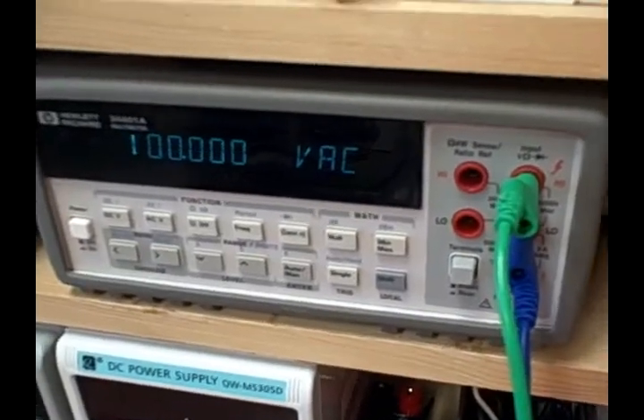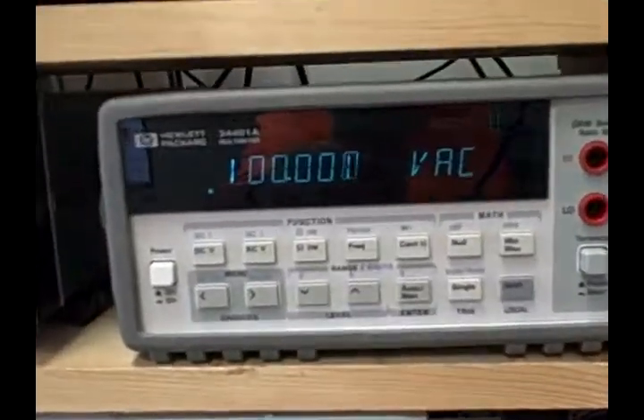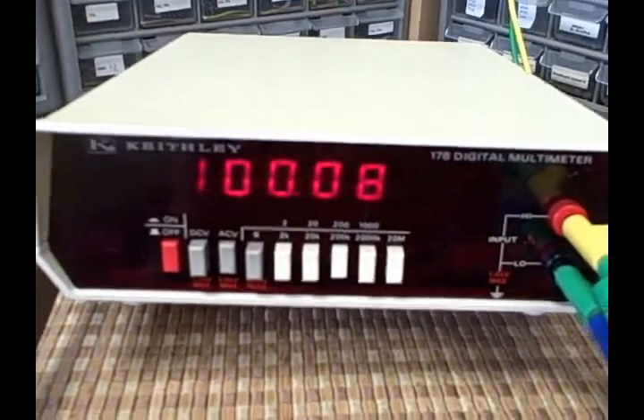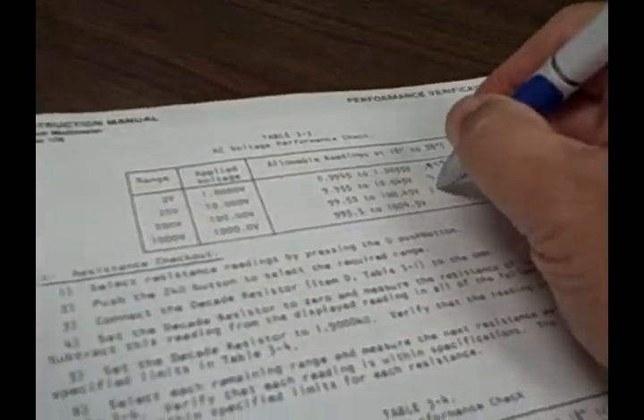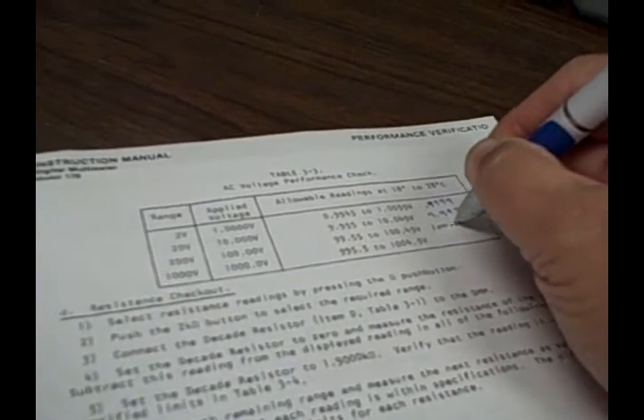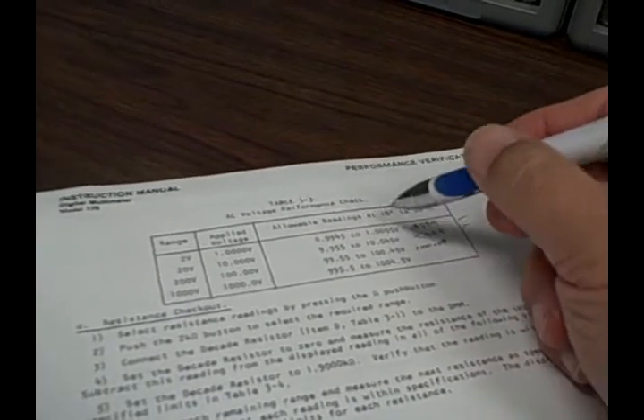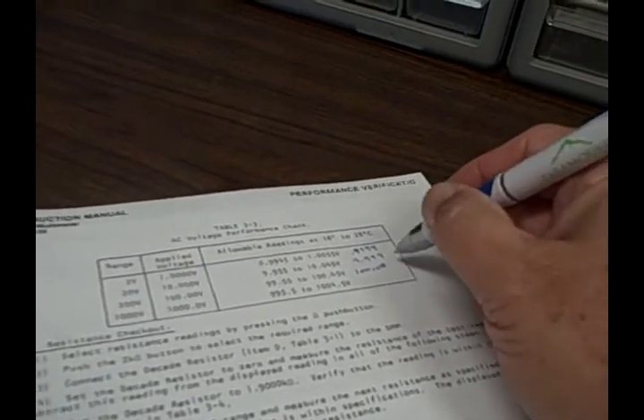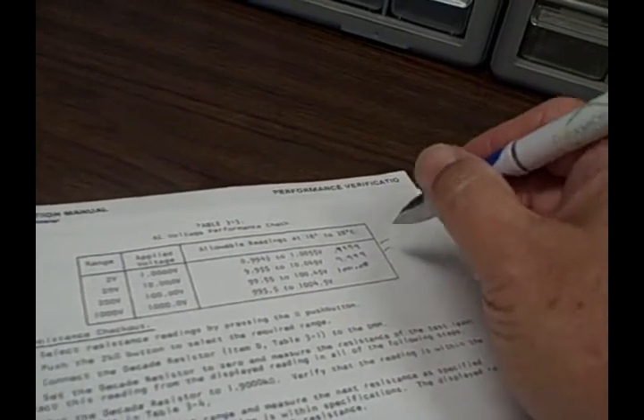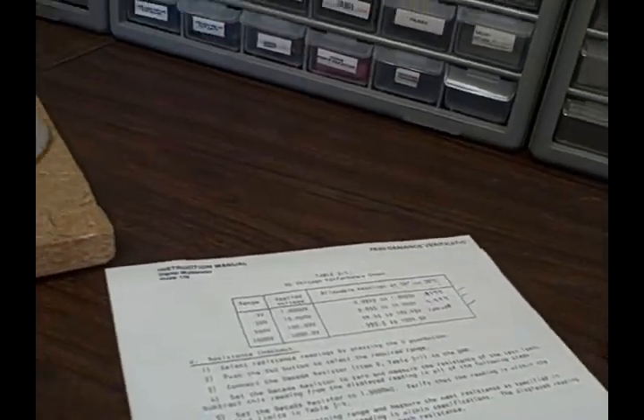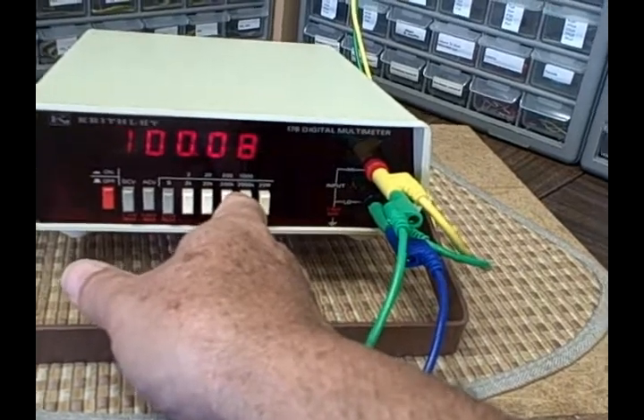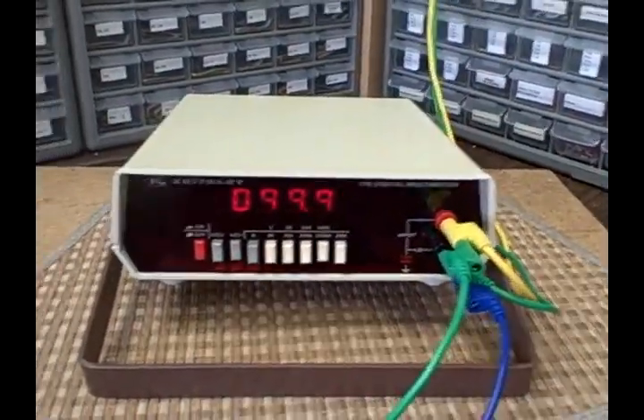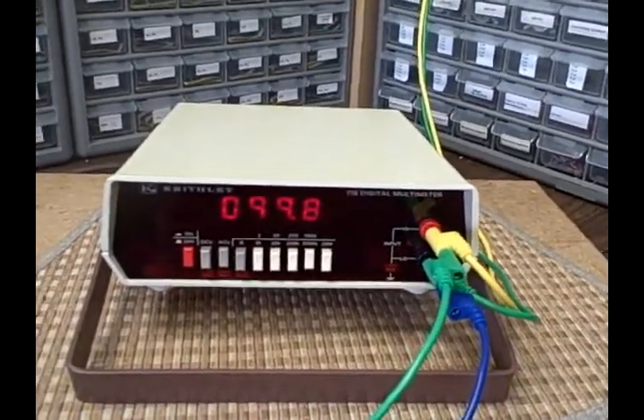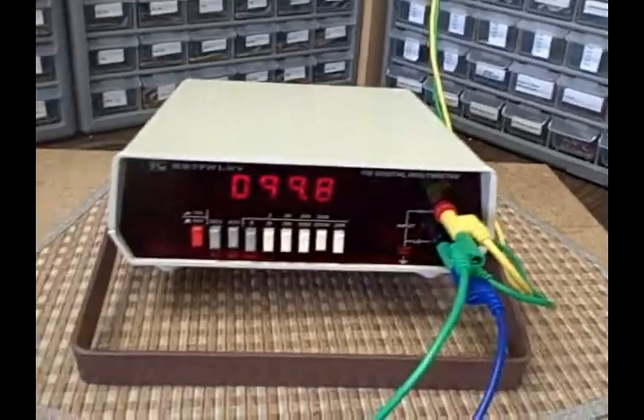Okay. All right, we got 100.000 volts AC. And we're getting a reading of 100.08. We would be accurate if we were between 99.55 to 100.45, and we're 100.08. So again, right in the middle. We are 0.08 of a volt off of perfection, but beautiful. And if we go to the 1,000 volt range, the best I'm going to be able to do here is about 120 volts input. I don't have the amplifier to allow me to go to 1,000 in AC. But let's go ahead and give ourselves the maximum that I have.